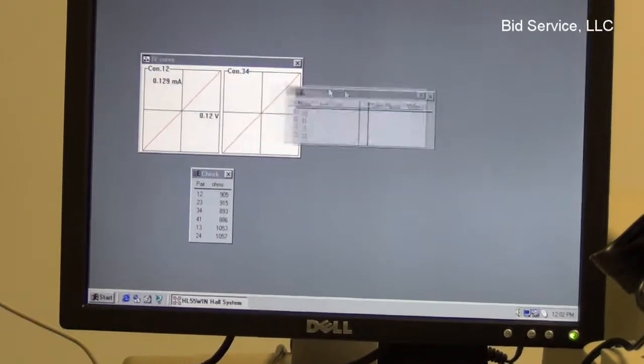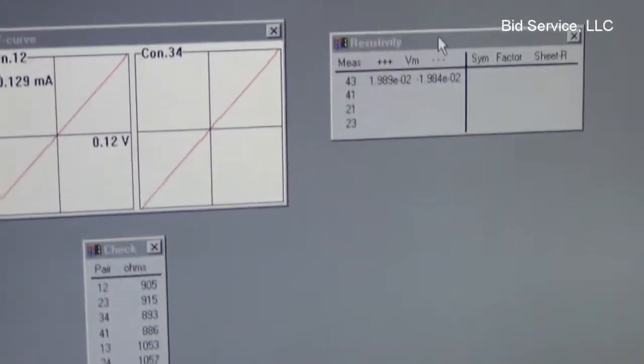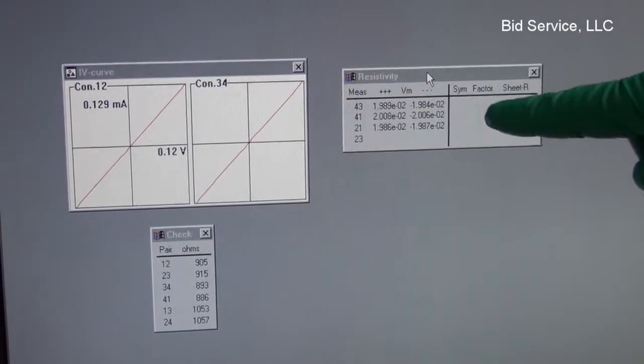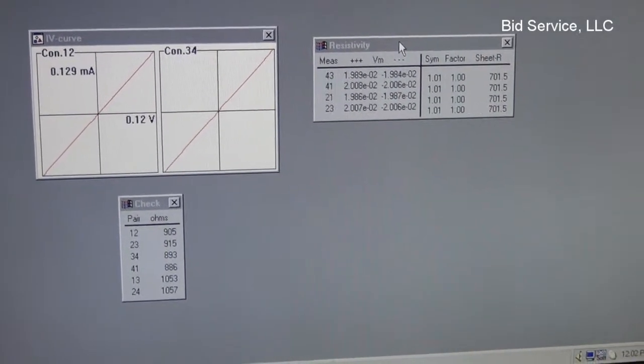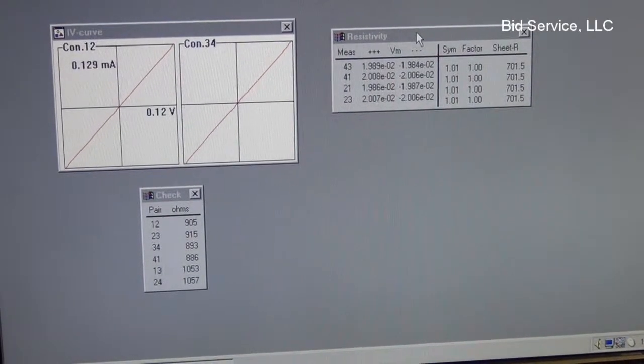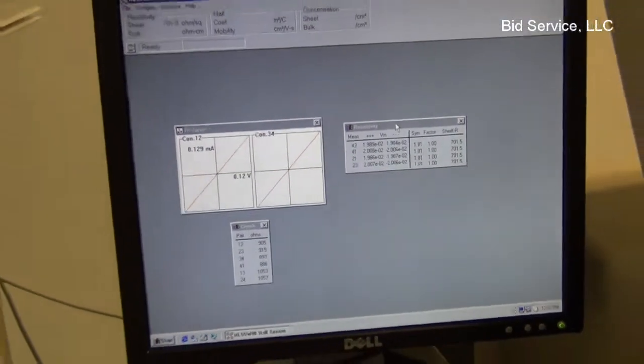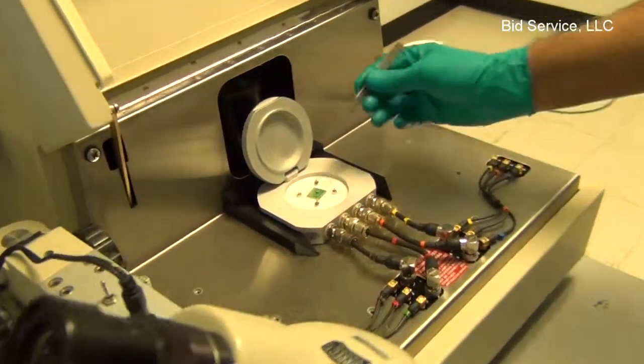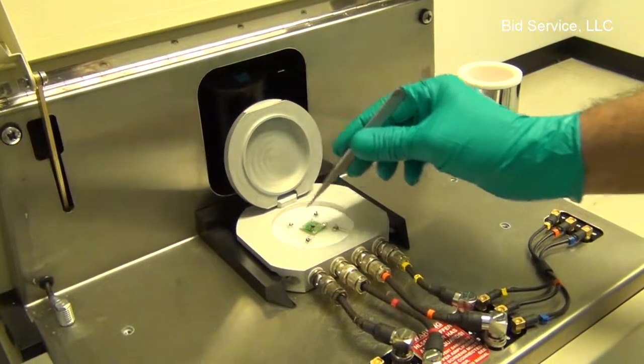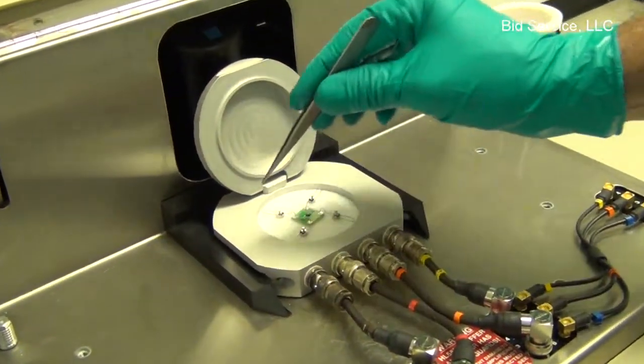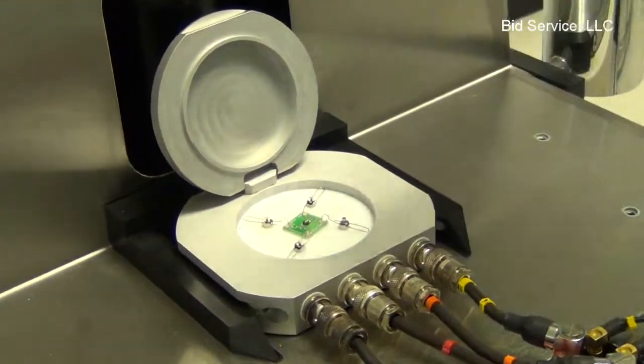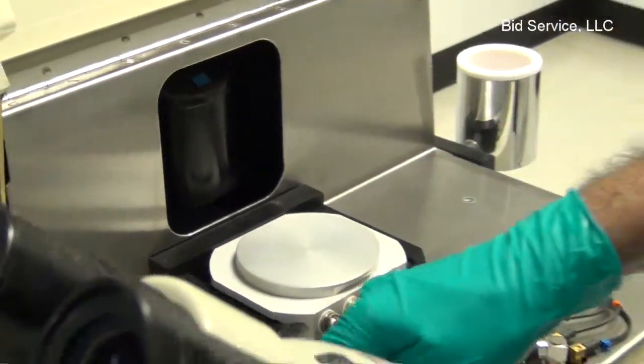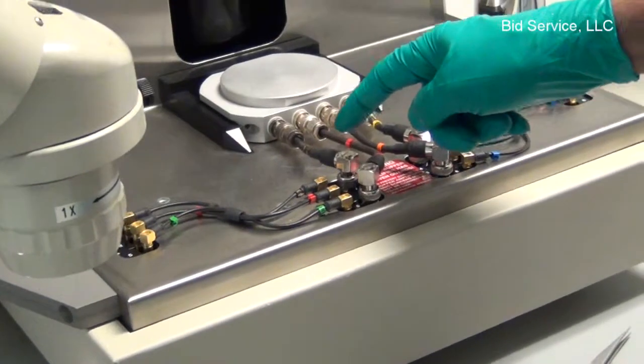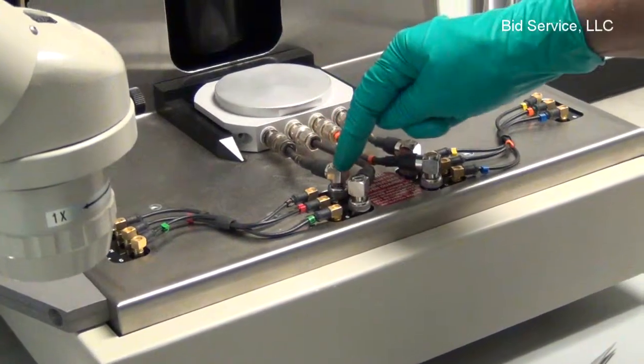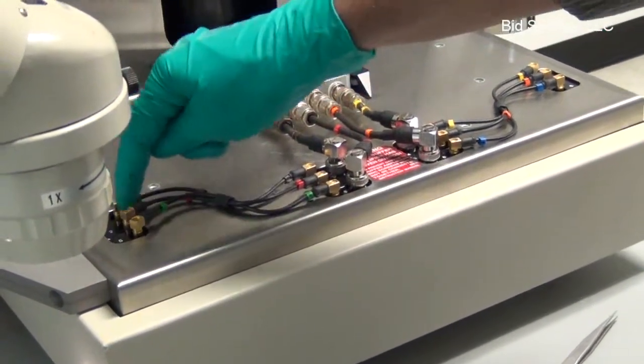Now I'm doing the resistivity check. And again, the measurements are between the contacts 4 and 3, 4 and 1, and 2 and 1, and 2 and 3. While doing the measurement, the unit will prompt to close the door if necessary. This is contact number 1 and 2, 3 and 4. They're in a counterclockwise pattern. 1, 2, 3 and 4. And all the probes are numbered on the connections as well. The coaxial wires are connected to these pins.